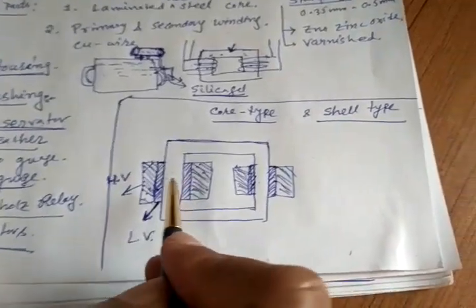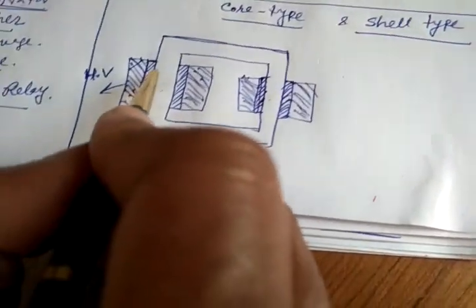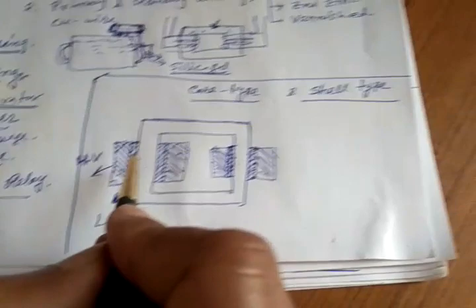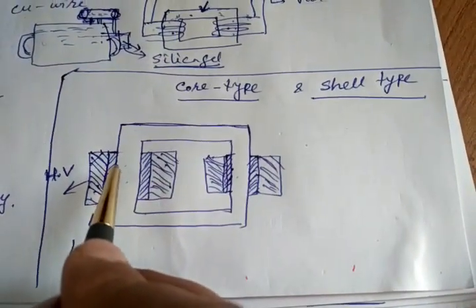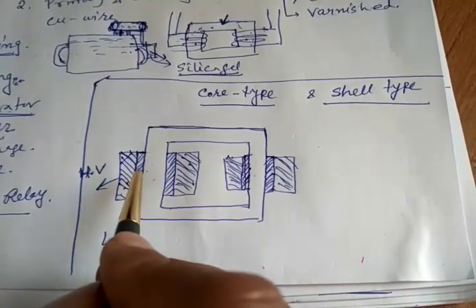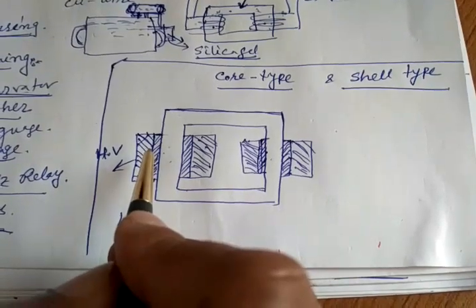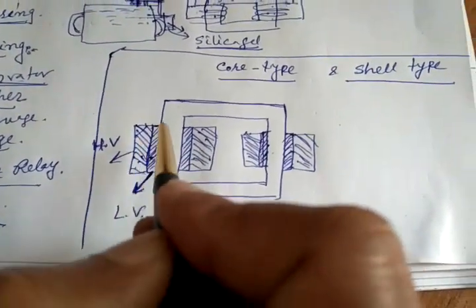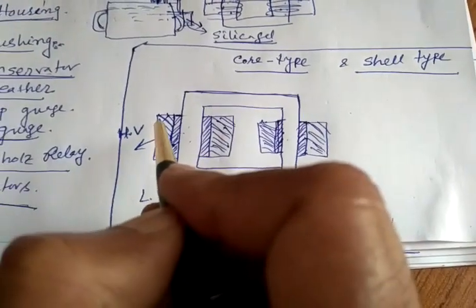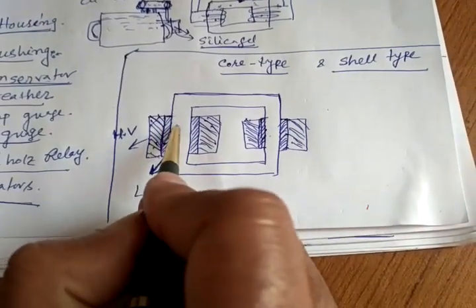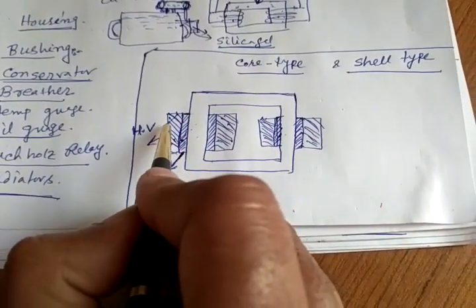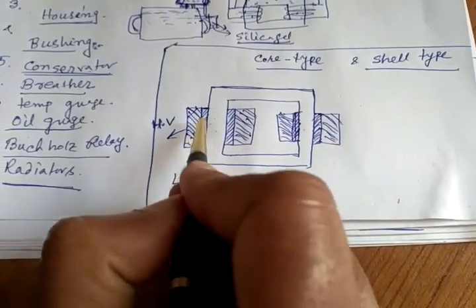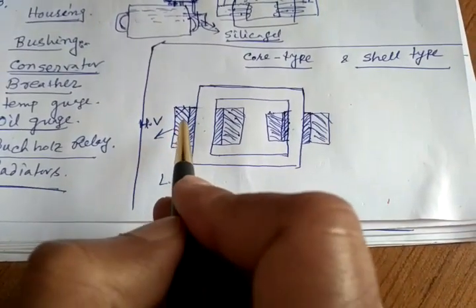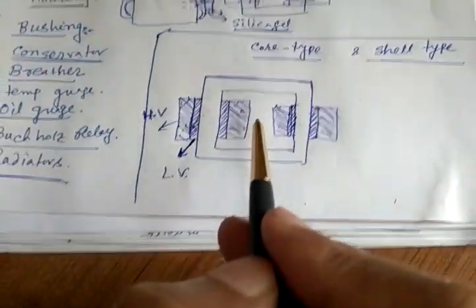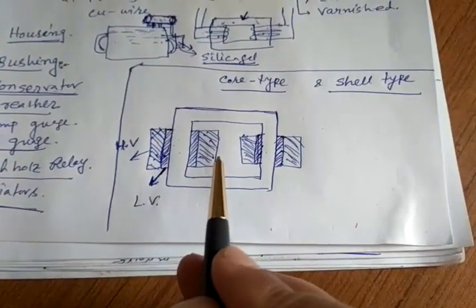Another advantage of this is that the mutual flux will be more, or you can say the leakage reactance, the flux component that goes out and does not link to the other coil, will be much reduced, because the high voltage coil is outside and the low voltage coil is inside, so flux linkage will be more. So we have very reduced leakage reactance.